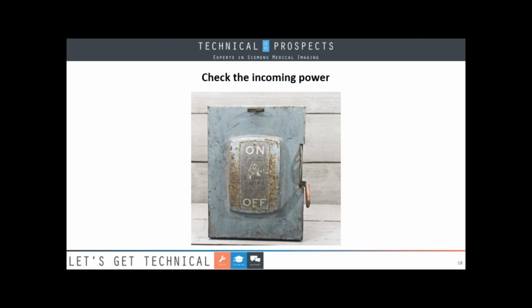All right. Do you have a service key? I had the privilege of working for Siemens for over 10 years, so I can really only relate to how to do it with Siemens, but they're fairly similar. It's easier to get a service key from Siemens if the person calling is in the Siemens database. Usually in your imaging center or hospital, someone has a relationship with GE or Siemens. If you don't, I would have that person call and say, I need a service key. If Siemens knows you, they're going to give you one, which is called a level 4 for about a year. That's pretty standard.